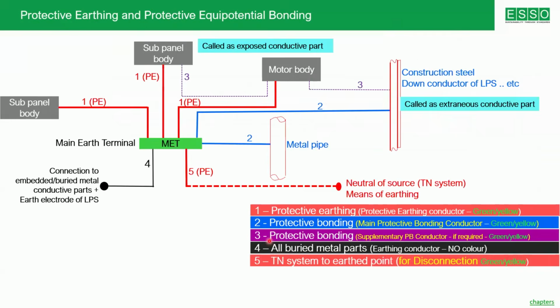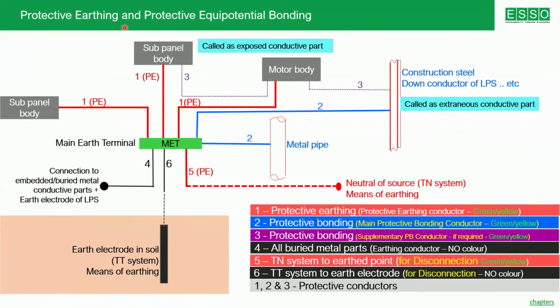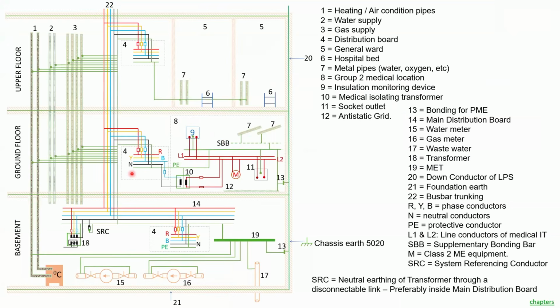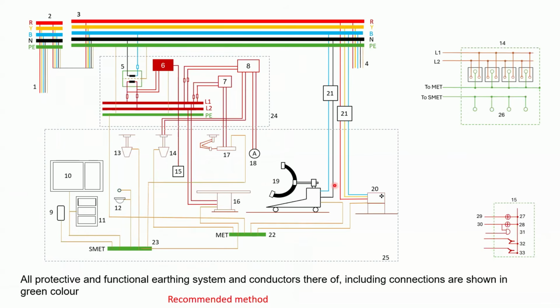The first subject, or one of the subjects which you cannot compromise, is protective earthing and protective equipotential bonding. That means you are creating an environment inside the hospital in such a way that potential differences do not exist. For this, the sizing of the conductor, the resistance of the conductor, the resistance of each of the joints, the touch voltages, all are important. The pictures, for example, this picture from a very old Indian standard, we at NFE had published our guide on electrical installation, or guide for hospital safety audit. You can find this picture in our NFE guide for hospital electrical safety audit. So here, how to make equipotential bonding is very much explained. How to make equipotential bonding in a group 2 medical location is very much explained.